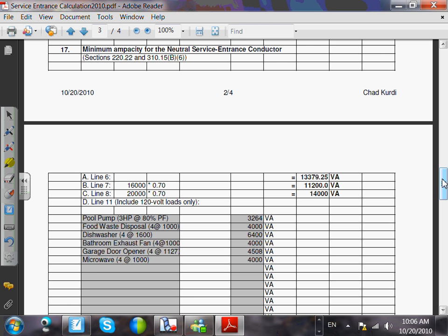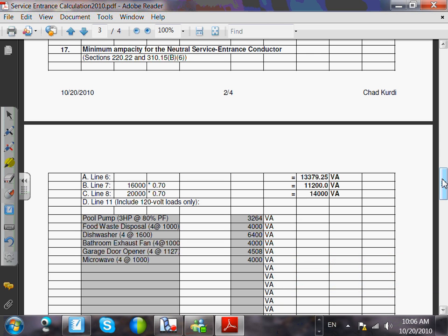Does that make sense? So that's why I went directly to 240.6. My panel could be a 600 amp panel, right? Do we have a 500 amp panel, single phase? We don't. So the actual size of the panel would be 600 amp, but my overcurrent protection device inside it would be 500. Is this okay? No problem. I can put 400 in there. I don't want to get into sizing the panel, but for the time being, stick with this: the size of the panel is the size of the overcurrent protection device, exactly based on the code.